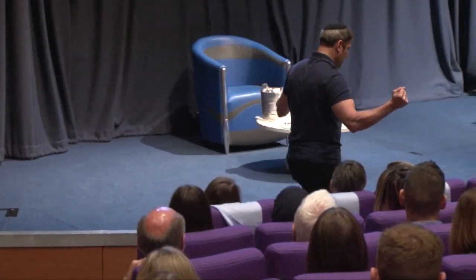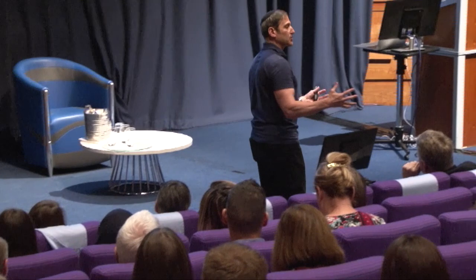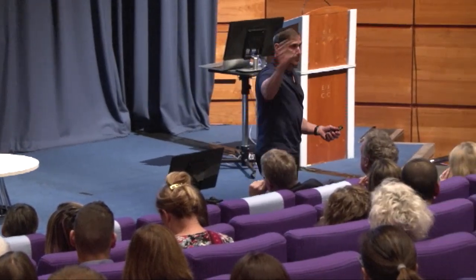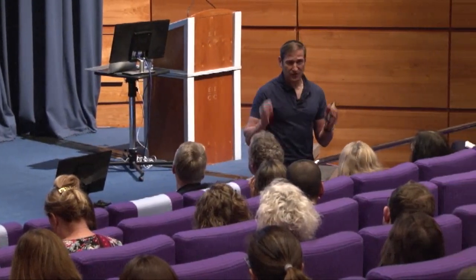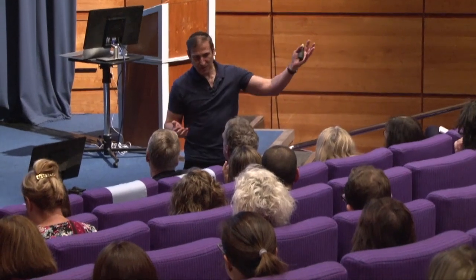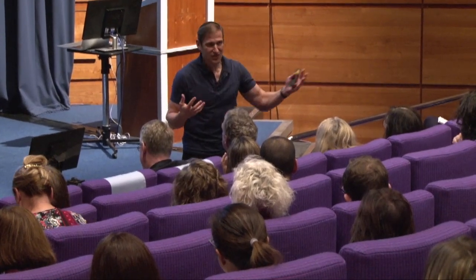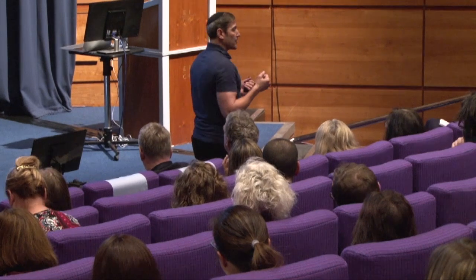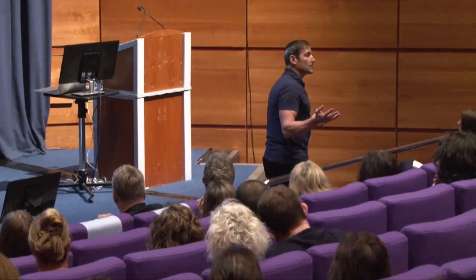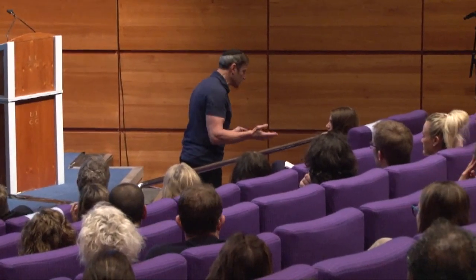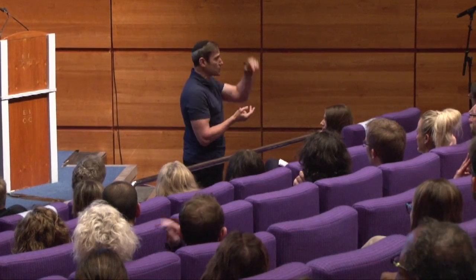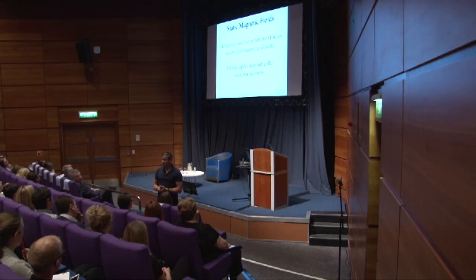Somebody brought me a fire extinguisher for testing. It says on the side MR conditionally safe, tested for MRI, and you can bring it in. It's aluminum, so it's not going to go flying into the scanner. We also tested oxygen delivery systems—not just the tank, but the tank, the stem, and the regulator together. That's an oxygen delivery system, and it says MR conditionally safe.